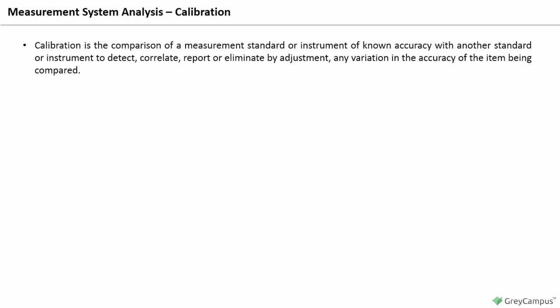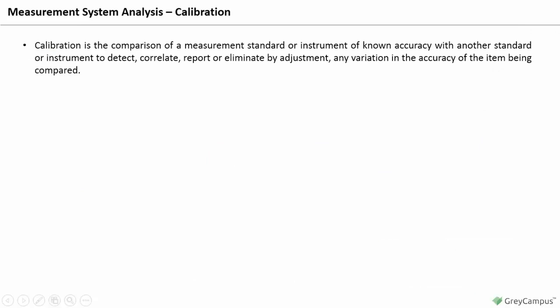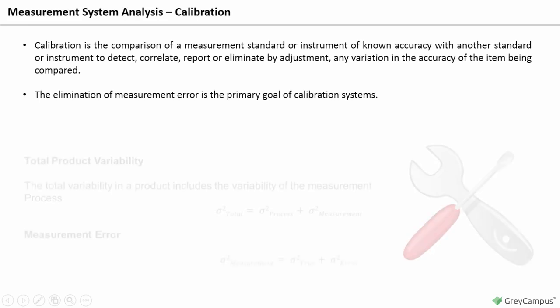Calibration is the comparison of a measurement standard or instrument of known accuracy with another standard or instrument to detect, correlate, report, or eliminate by adjustment any variation in the accuracy of the item being compared. The elimination of measurement error is the primary goal of calibration systems.